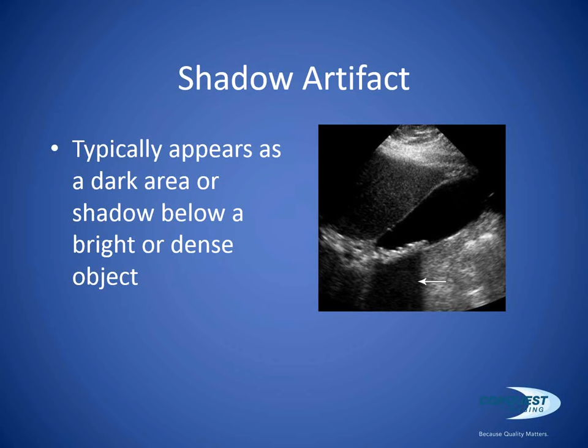And then artifacts and noise. This is very timely. The site that I'm at today is experiencing noise in a couple of departments on a couple of different machines. One is a Philips EPIQ 7, and the other one is a Philips IU22. Not that I'm bagging on Philips. They all experience them. In fact, the images that you see in front of you now are a GE Logiq 9 that was experiencing some noise. Noise problems are by far the most difficult problems to troubleshoot.